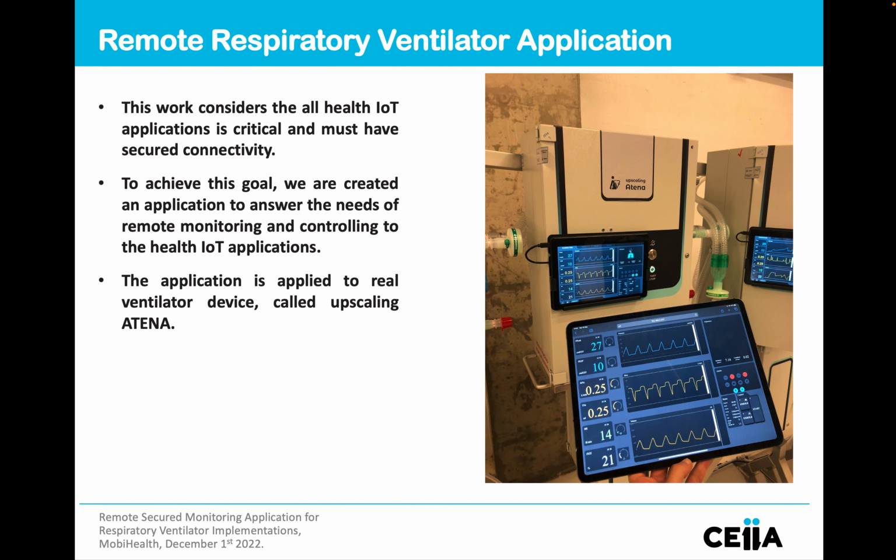So as you can see here in the image, we have the display from the ventilator, and we have a tablet that's showing the remote application, and you can see that both of them have no visible delay on the data. In the plots that you see, the white bar is almost in the same place, so our eyes could not detect the delay between the data collected by the ventilator and the data seen in the remote application.